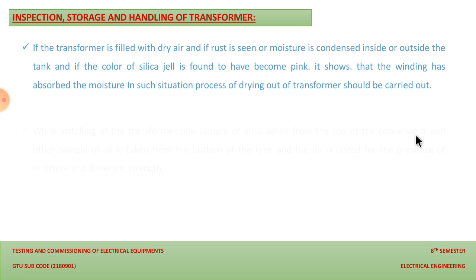While installing the transformer, a sample of oil is taken. So while you install a transformer, if the transformer is oil filled, the sample of the oil is taken from the top of the conservator, the conservator where we put the transformer oil, and another sample of the oil is taken from the bottom, from the mud cock, where we have the slurries and other contamination we receive after certain use of the transformer. So from these two sides we take the sample of the oil, and the oil is tested for the presence of moisture and the dielectric strength.